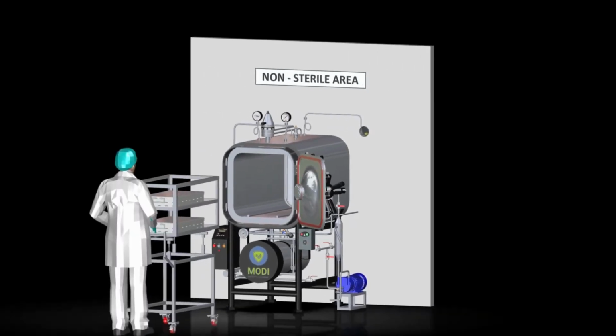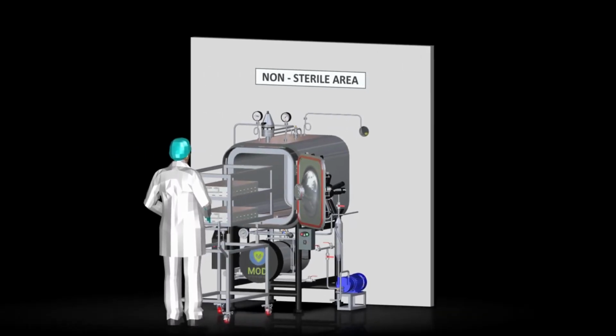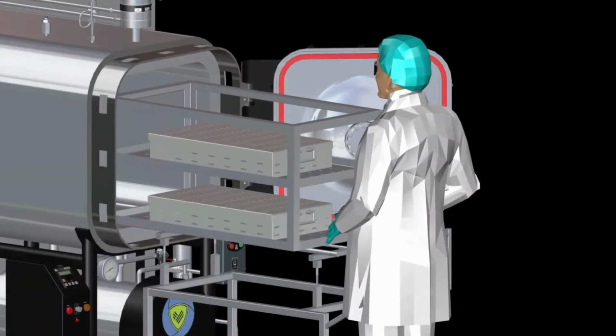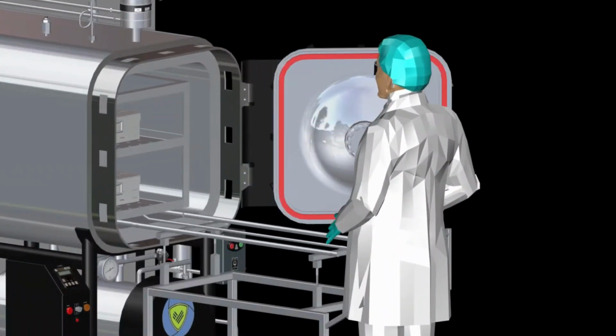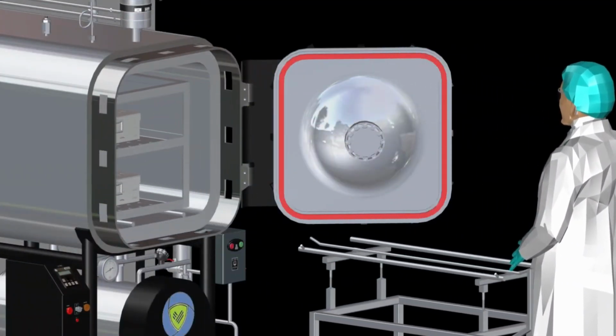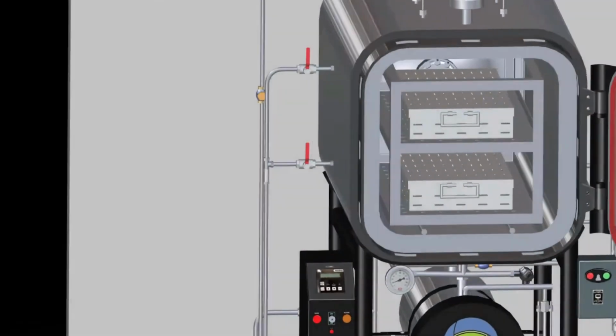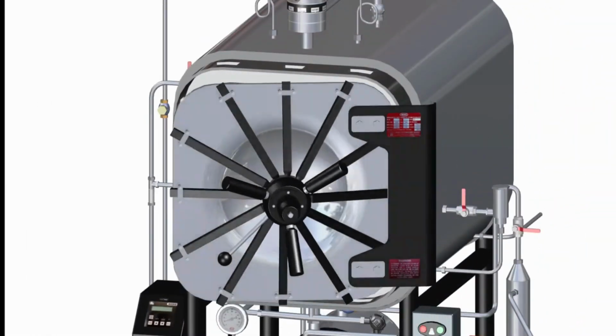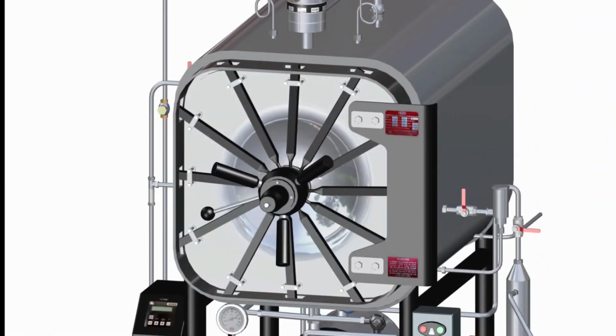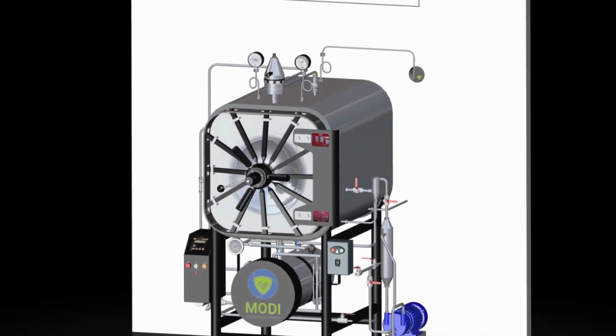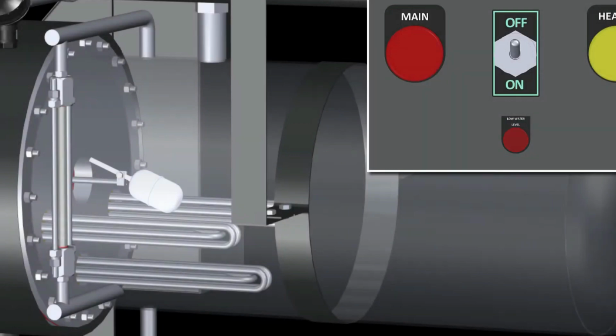Items are packed in such a way that steam can easily penetrate all surfaces. Seal the door. The door of the autoclave is securely closed, ensuring a proper seal to prevent steam leakage. Cycle initiation. Air removal. The cycle begins with the removal of air from the chamber, as trapped air can interfere with effective steam sterilization. There are different methods for air removal.